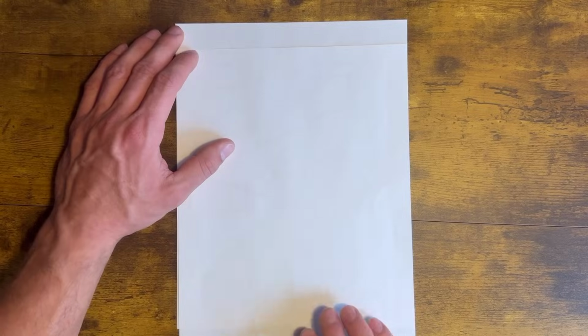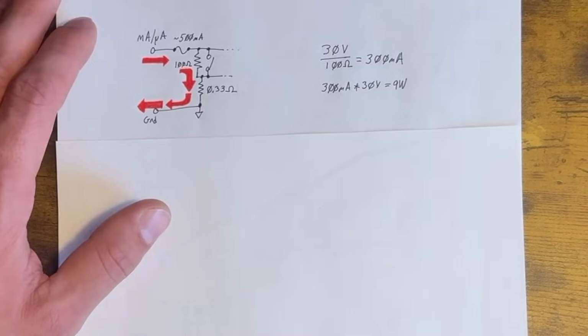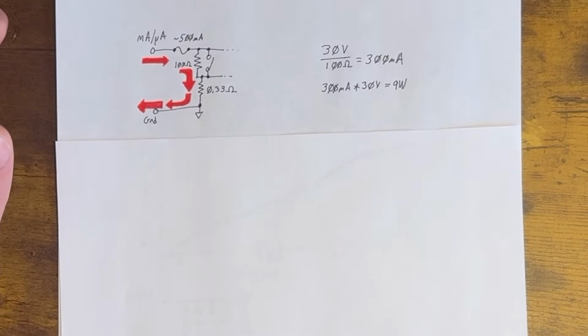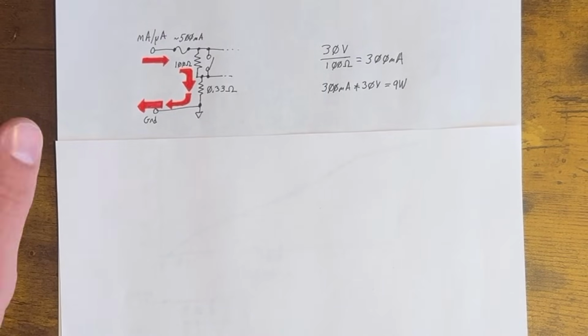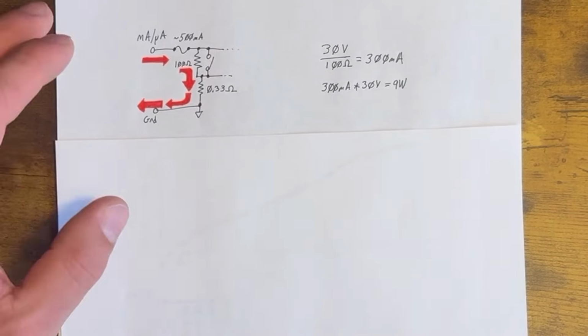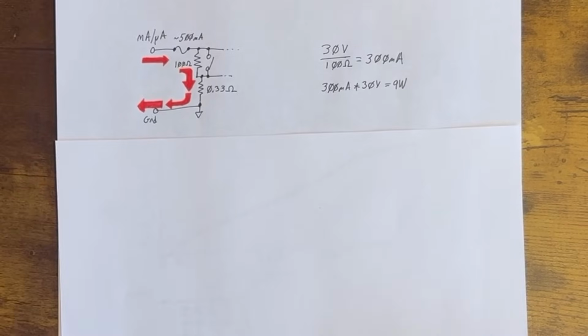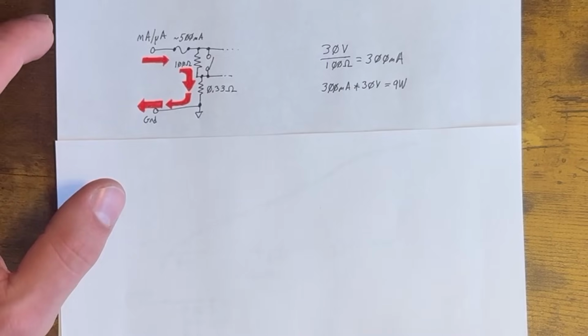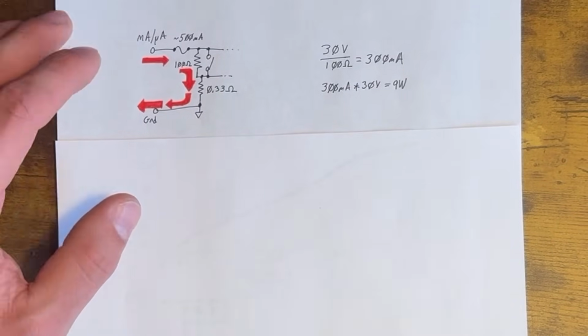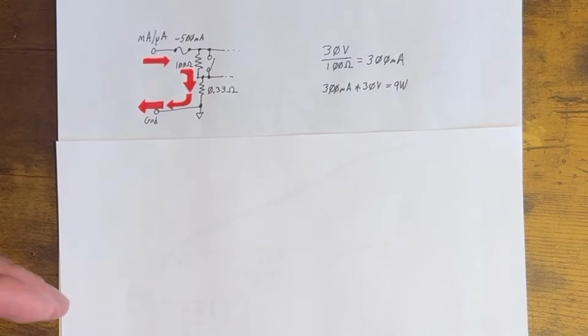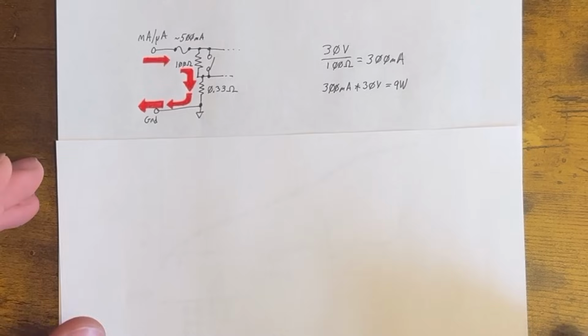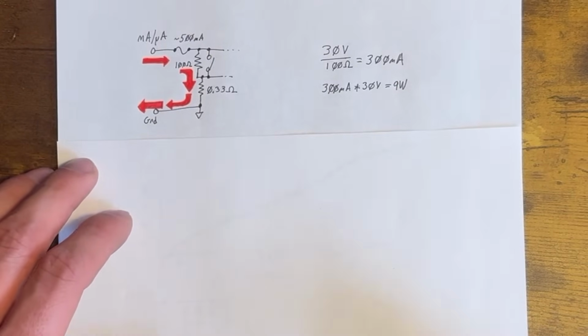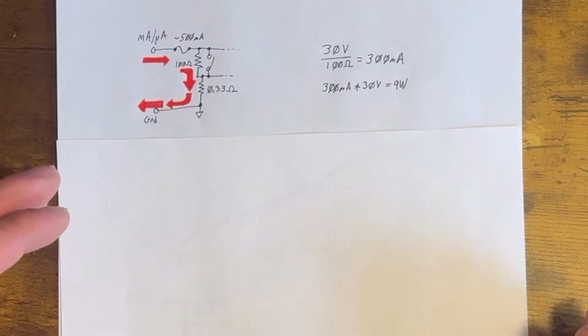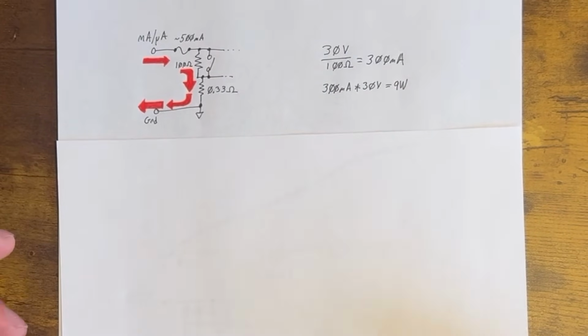Looking at the circuits, the main danger is that voltage can build up across the shunts. There are two failure modes here. One is that we put too much current through the microamp range. It won't blow the fuse, since it's rated for about half an amp, but we can dissipate a lot of power — somewhere around 10 watts in our little 1206 resistor. This will fry it in no time, probably even desolder it from the board. So what we need is something in parallel that passes effectively no current at low voltage, but above 1 or 200 millivolts, our burden voltage, starts to conduct, and conducts very strongly before, say, a volt.